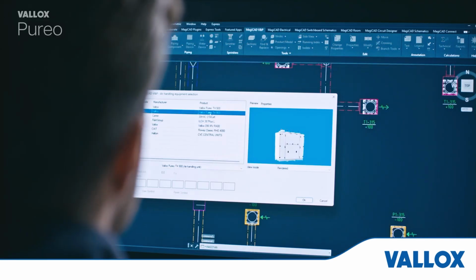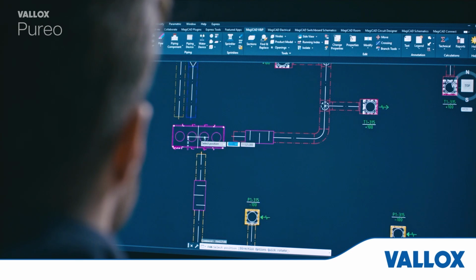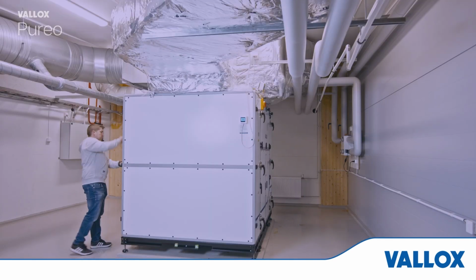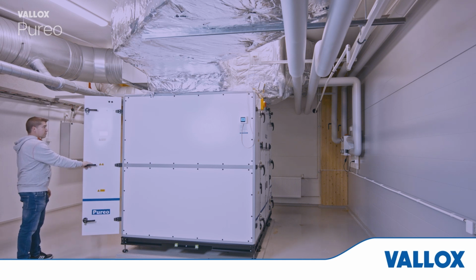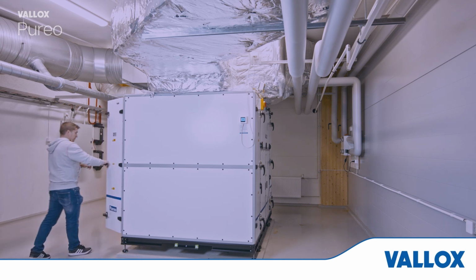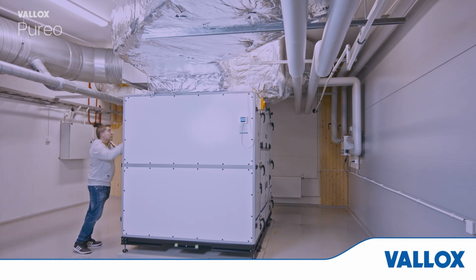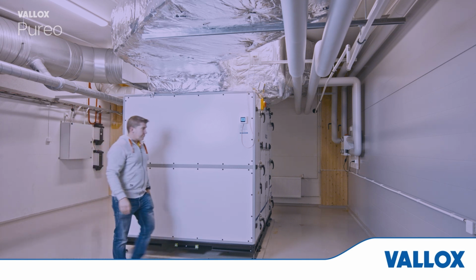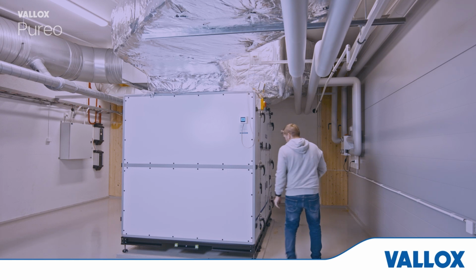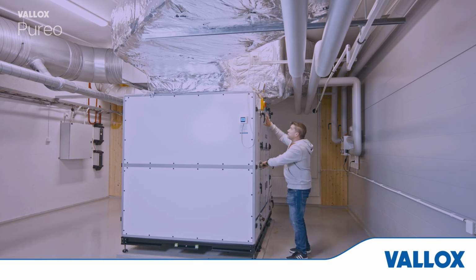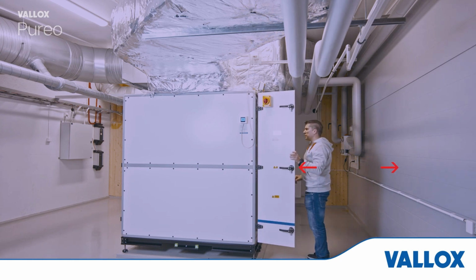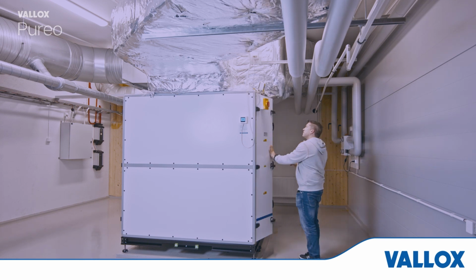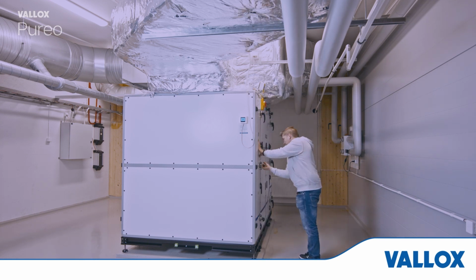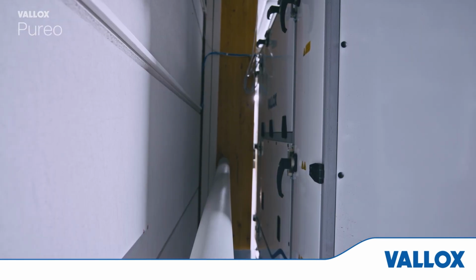When planning the installation, enough room must be reserved around the unit to ensure smooth maintenance. When installing the unit, make sure that there are no immovable obstacles in front of the unit and that the doors can open 90 degrees. This makes removing the cell and filters easy. If there is enough space, the unit can be serviced from either side. See the unit manual or the Vallox Pureo selection program for the required minimum clearances. If the unit is installed against a wall, it can be maintained only from one side.